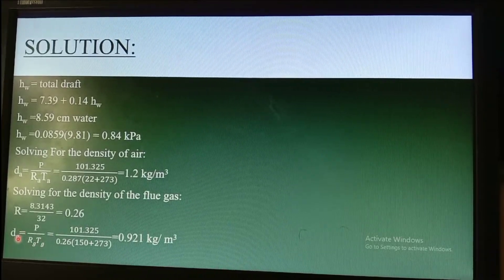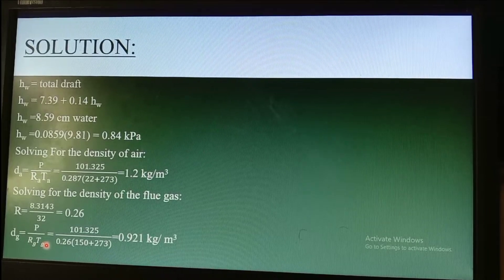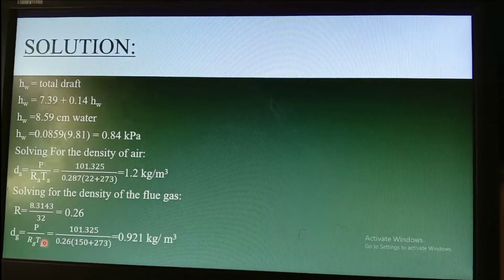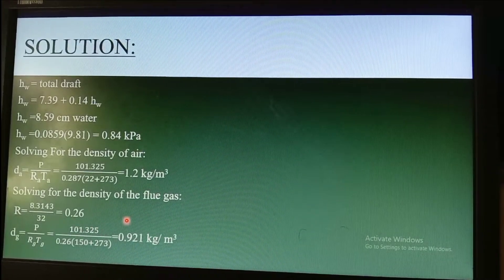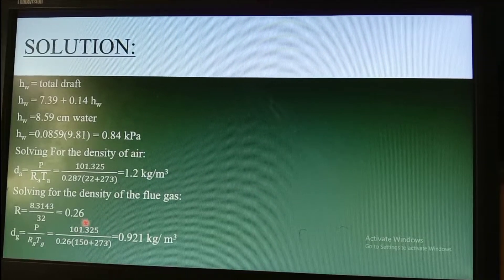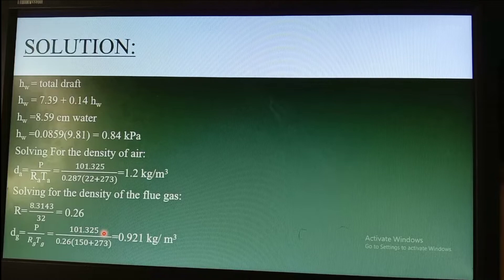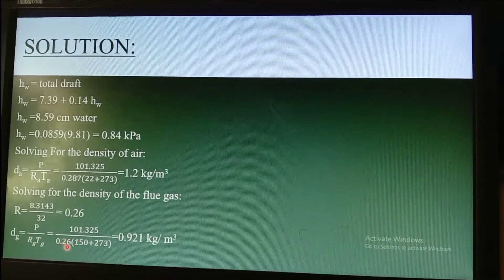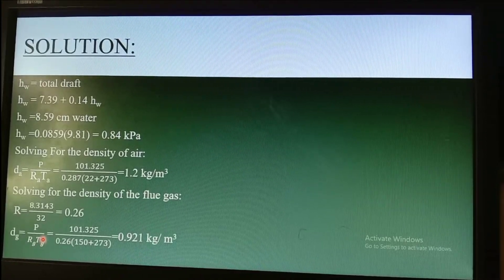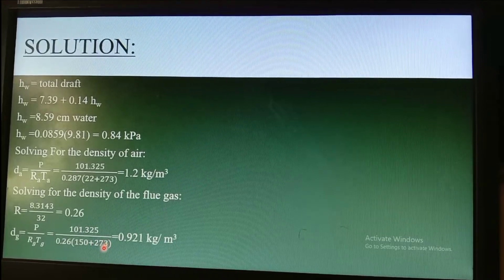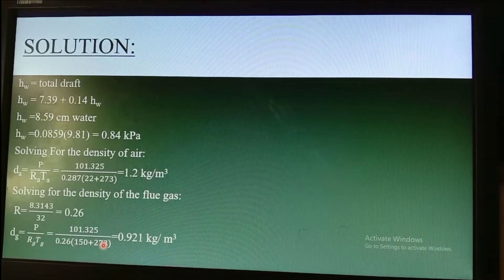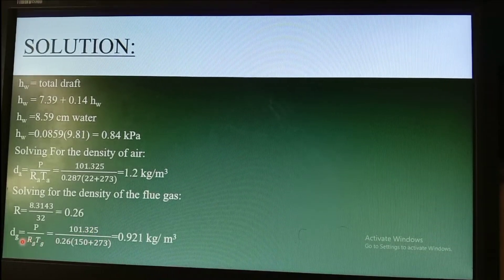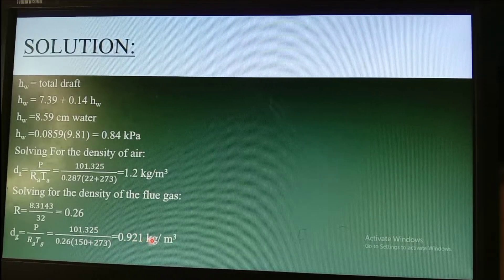Solving for the density of flue gas: Dg = P / (Rg × Tg) = 101.325 / (0.26 × (150 + 273)). We add 273 to convert degrees Celsius to Kelvin so all units are consistent. The density of flue gas equals 0.921 kilograms per cubic meter.